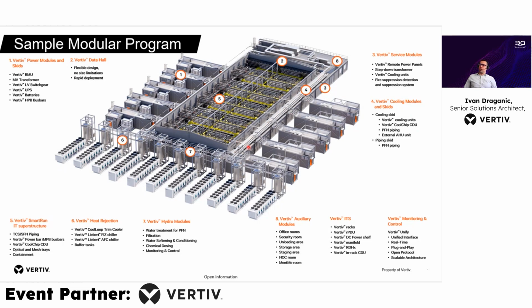We also have some of the cooling corridors on the outside and the cooling modules, which are basically used to reticulate the bus bars, so the power and the cooling all around the data center. These data centers feature concurrently maintainable power and cooling topologies, and that's all installed on these kits that go around. Number 6 is the heat rejection skid. It's basically a continuous cooling tank that's coupled with a trim cooler or a traditional air-cooled chiller. The trim cooler is something we use exclusively for the GPU cooling loads mostly, because the GPUs nowadays can take temperatures up to even 45 degrees. Which means the trim cooler is basically a dry cooler that will operate in dry cooling mode most of the year, but it also has the compressor installed, so it can ramp up the compressor and take care of the peak loads during the summer.